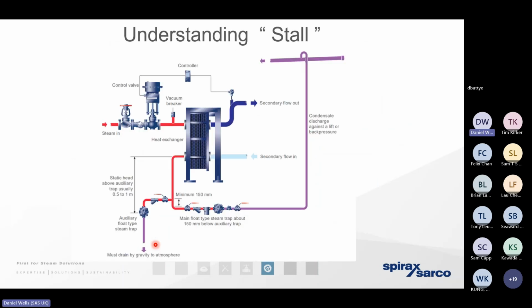So I want to come to a concept, an issue that we refer to as stall now. I contradicted myself a little bit last week because I mentioned that there's actually more heat energy present within steam at lower pressures than there is at higher pressures. So when we look at heat exchangers, we want to condense the steam at the lowest pressure we possibly can to squeeze out the maximum energy content from that steam.